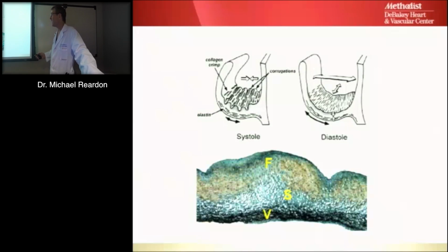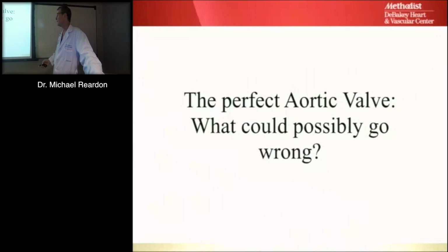We're going to ask Jeff questions now that he's here. One of the problems we had with early tissue valves is they'd take a pig valve and mount it on a frame. When they mounted it on the frame, they would fix it under pressure. And what happened? You took all these little corrugations and ironed them out. So it no longer had this nice little elastic stuff that let it open and close, but it was rigid. Instead of having a piece of elastic, it's like having a piece of cardboard. If you bend a piece of cardboard, what happens? It bends at one spot. And that one spot bent over and over and over again, and those valves all failed. So we learned to fix them with no pressure.